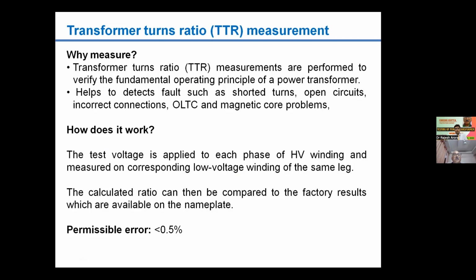Transformer turns ratio is also measured. Basically, ratio measurements are performed to verify whether there are any issues inside the transformer, whether some shorted turns are there, or some open circuit has taken place, or some problems are there with the core, etc. So basically, magnetic circuit and the winding integrity are checked through this test.